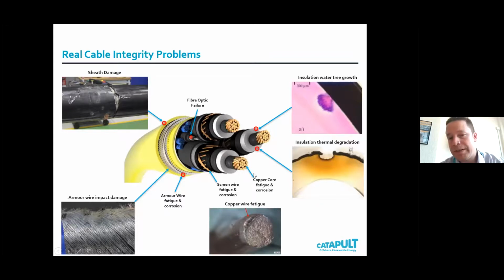Probably the most fatigue sensitive components of these systems are the copper. So you've got these screen wires and you've got the copper cores. When you bend back and forwards, that bending can cause fatigue. And something to think about here as well: it's not just a pure bar-bending fatigue. These wires are all sitting on top of each other. As they sit on top of each other, they contact, and that small area of contact can start a fatigue crack, and that's called fretting. So that's another thing you've got to think about.